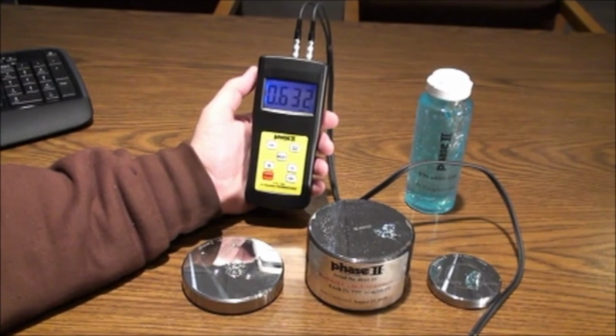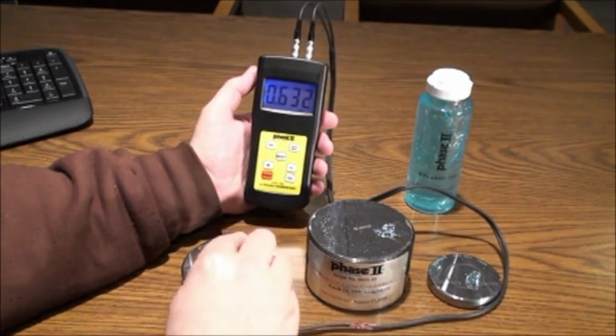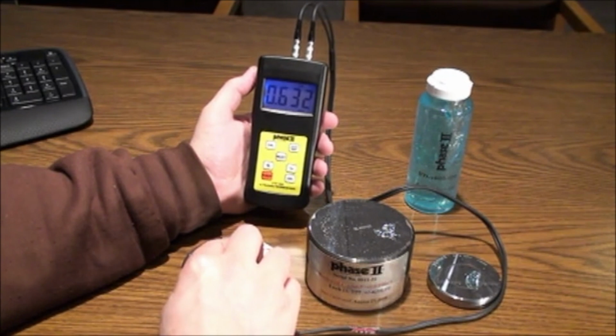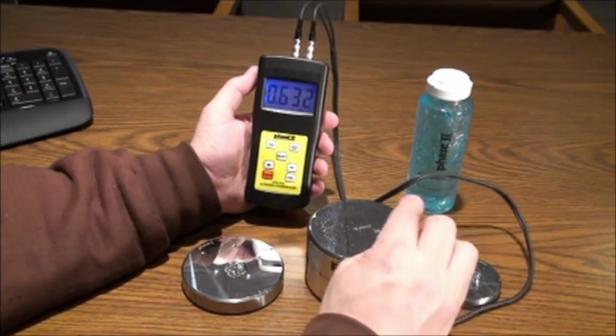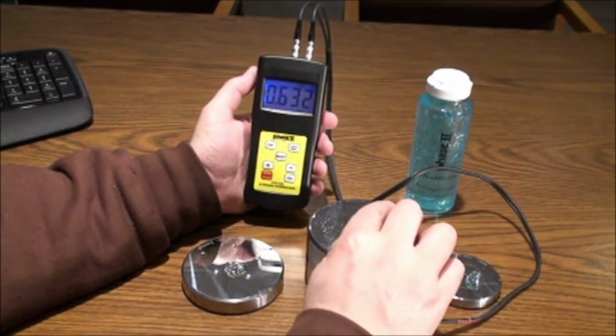Now that the unit is calibrated, you can begin to test your material. Make certain to select the material code, add gel to your workpiece, and press the probe to your surface. Don't forget, if you have other material than the preset codes, you can enter CD12 and manually enter the correct sound velocity for your material. This can be referenced from the chart provided in the manual.